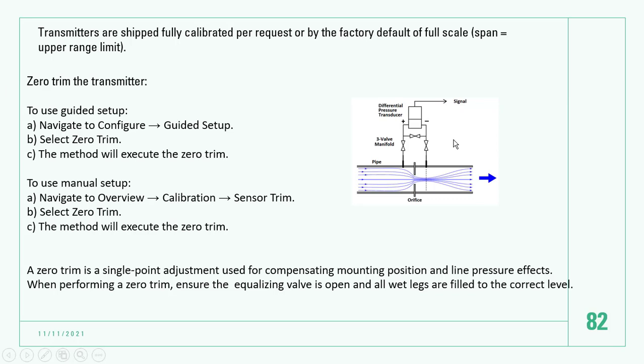How to zero trim? First, close this valve, then open this valve, then the upstream side pressure equals the downstream side pressure. After that, close this valve. Okay, this pressure here equals here pressure. Then you can do the trim.